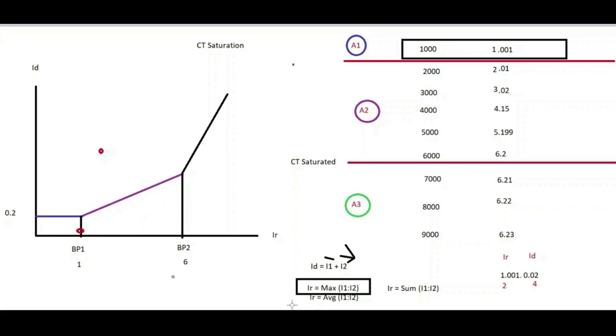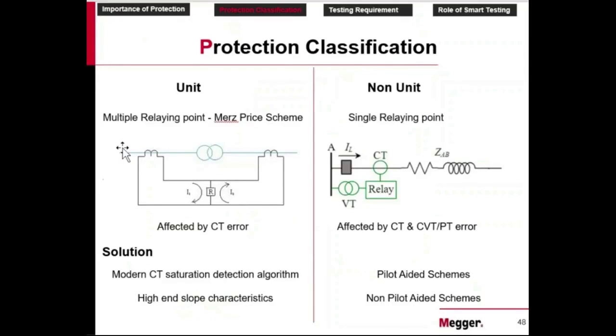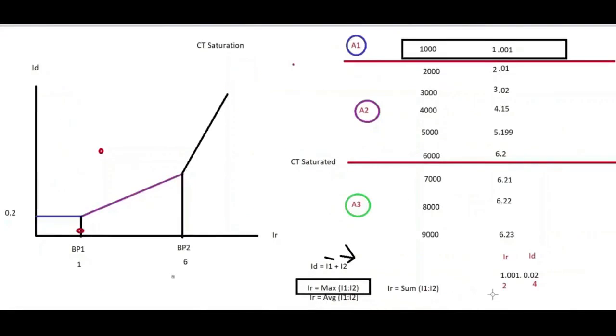Now let us take an example 3. Fault outside. Here. Fault is here. Let us assume same 2000 amps. So since the fault is outside, this direction will not change. We already saw this. So if the direction is not changing, what will happen? Your differential current will be theoretically 0, practically maybe some error. And your restraint current is still 2 amps. Right? 2, 0.02. So let's plot that. 2 is somewhere here. And 0.02 is definitely below the curve. So that means you can see the relay does not trip because it is below the curve.